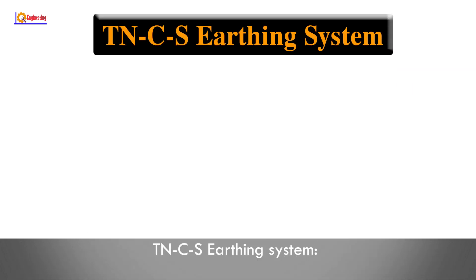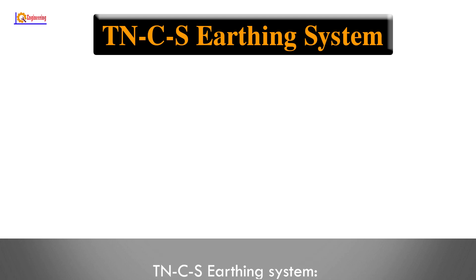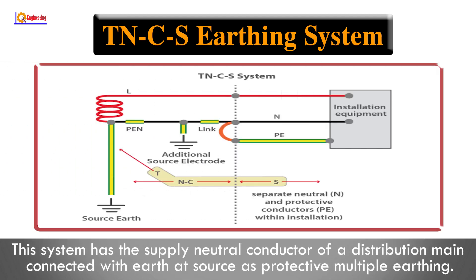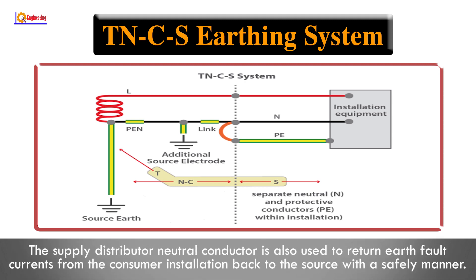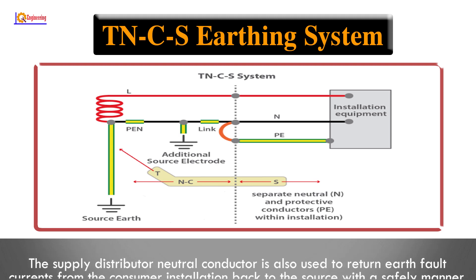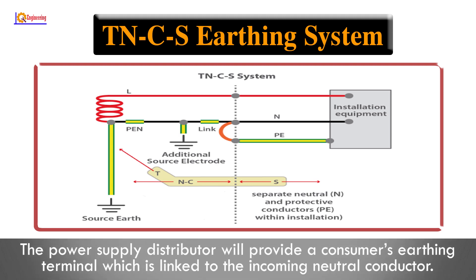TN-C-S earthing system: The supply neutral conductor of a distribution main is connected with earth at the source as protective multiple earthing. The supply distributor neutral conductor is also used to return earth fault currents from the consumer installation back to the source in a safe manner. The power supply distributor provides a consumer's earthing terminal linked to the incoming neutral conductor.